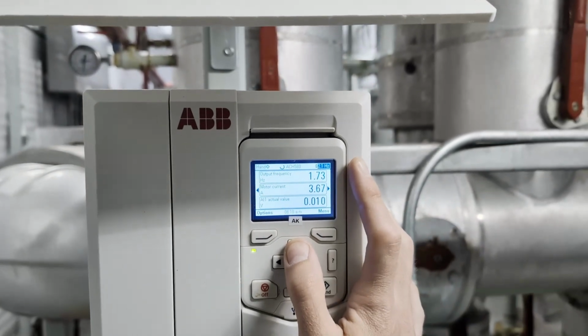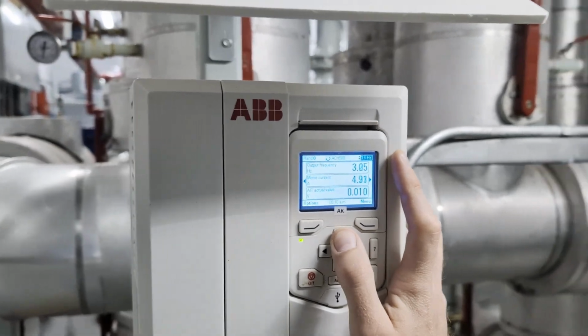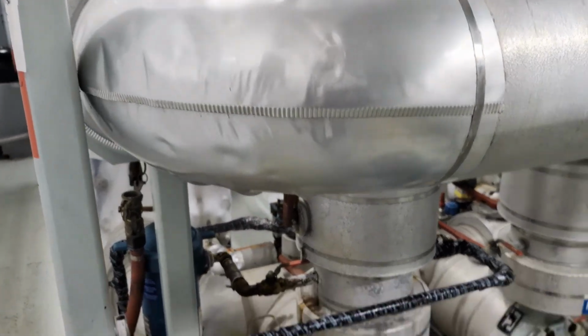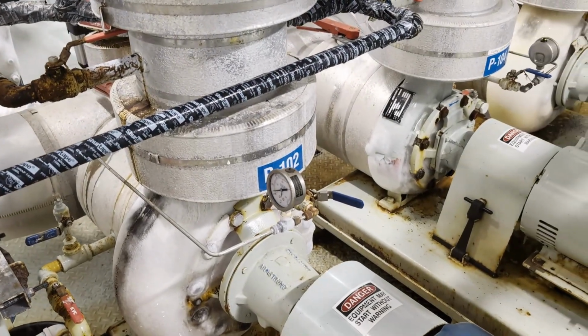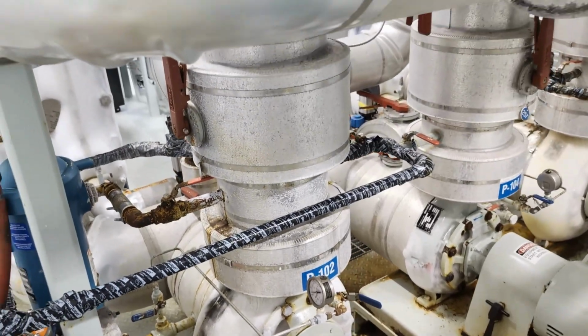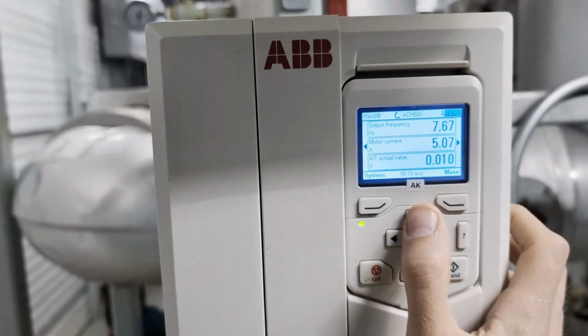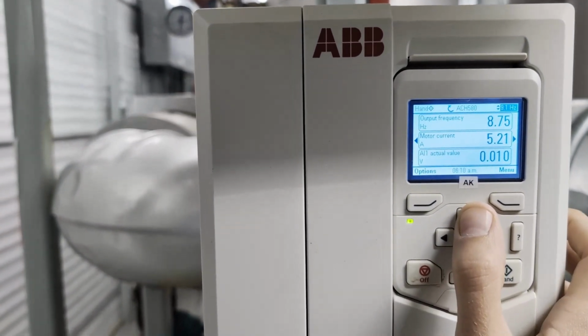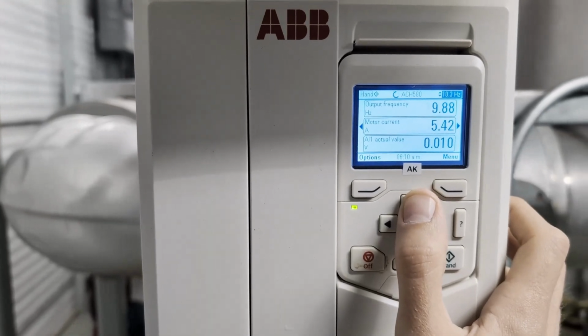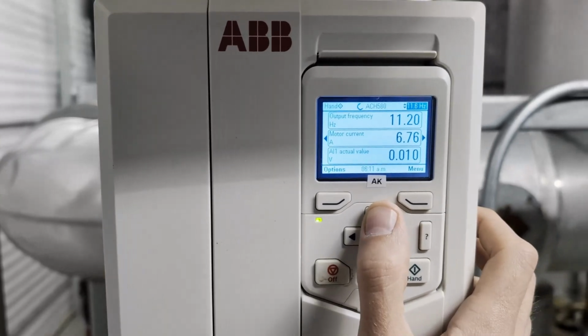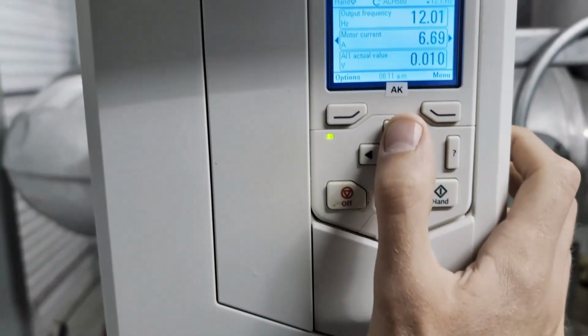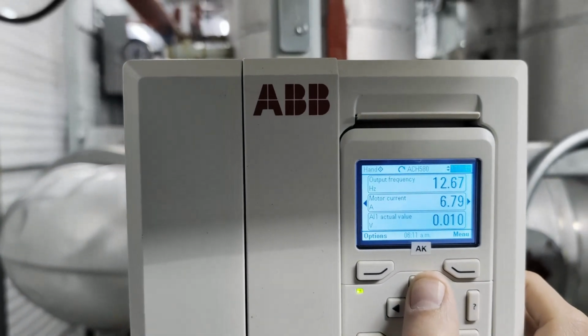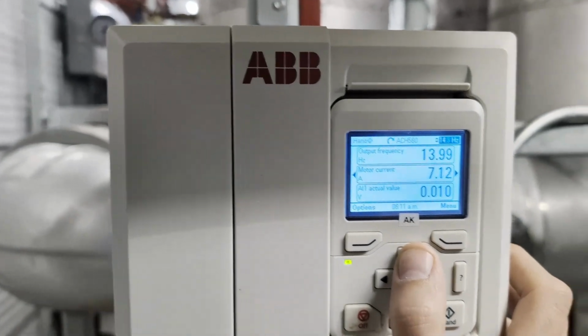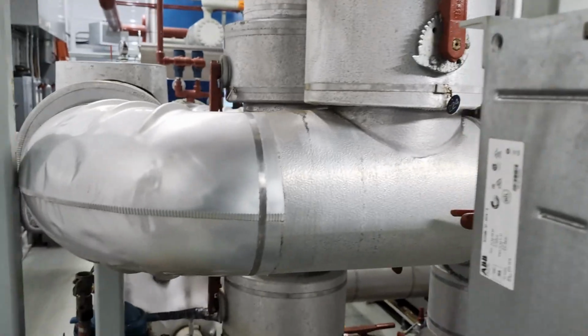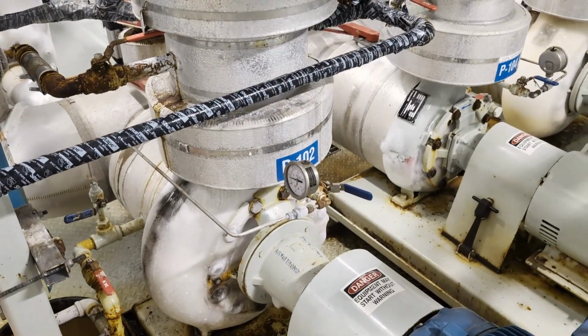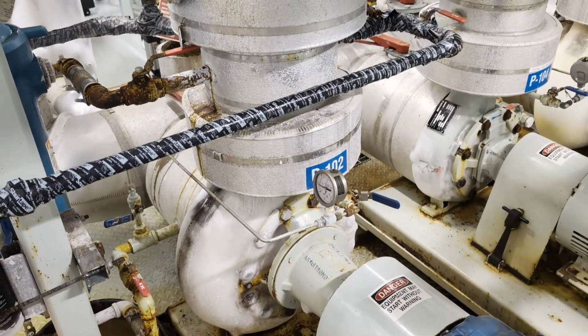So you can see as I ramp the pump up manually, you look at the pressure gauge, you're not really seeing much yet. That's because you need a certain amount of pump speed in order to actually get the brine to start moving. Right now I'm at about 12 hertz, so I'm still pretty low on the pump curve. But if you have a look at the gauge, you see it's starting to build a bit of pressure there.